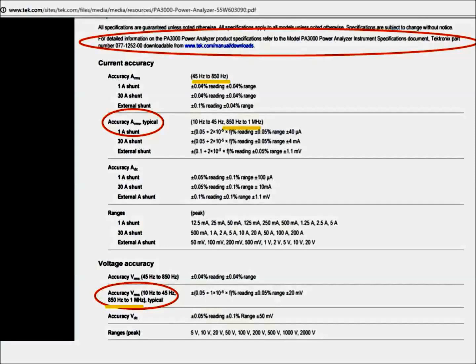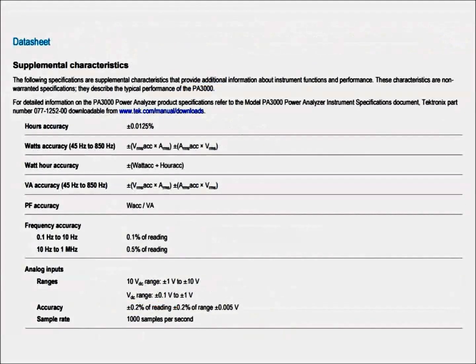Finally, peak ranges and RMS accuracies. I suspected this earlier when clipping occurred on the wave graph. Another confirmation of the power accuracy. As I understand though, watts is a unit of active power, which accounts for voltage, current and phase. Yet the accuracy specification here is just voltage and current. So that for me is either apparent or reactive power. VA though is listed underneath, yet it has exactly the same calculation next to it.